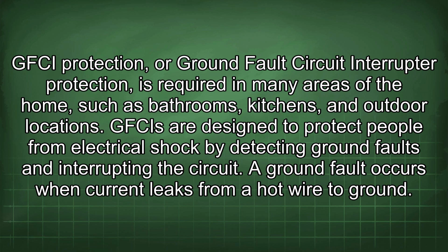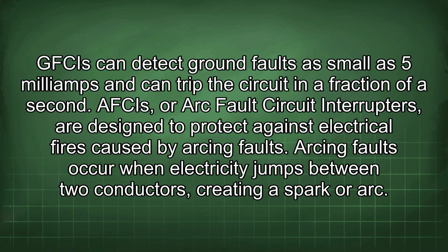GFCI protection, or ground fault circuit interrupter protection, is required in many areas of the home, such as bathrooms, kitchens, and outdoor locations. GFCIs are designed to protect people from electrical shock by detecting ground faults and interrupting the circuit. A ground fault occurs when current leaks from a hot wire to ground. GFCIs can detect ground faults as small as 5 mA and can trip the circuit in a fraction of a second.